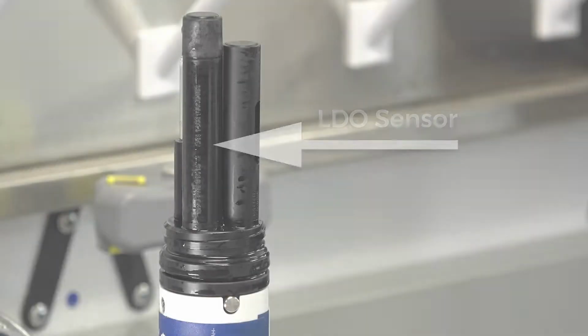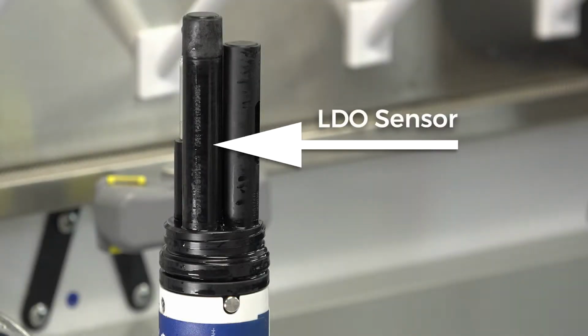Maintenance and calibration of luminescent dissolved oxygen, also known as LDO. The Hach LDO probe measures the oxygen dissolved in water by flashing a blue light on the sensor cap coated with a luminescent material and measuring the time it takes for the sensor to return red light. There is a red reference LED that provides an internal reference for the optical and electronic signal paths. This internal reference provides measurement stability by correcting for temperature or time-induced changes in the phase measurement electronics.